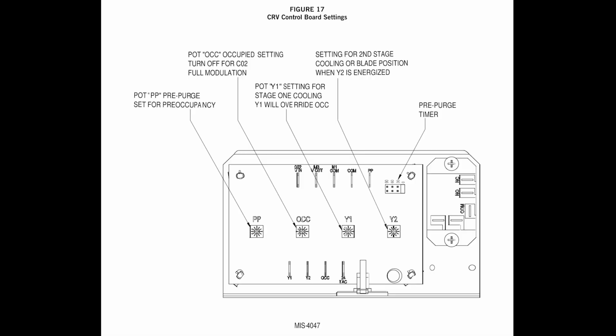The potentiometer marked PP is for pre-purge or pre-occupancy required by Title 24. Pot OCC is the occupied setting and must be turned off if a CO2 sensor is used. Pot Y1 or Y2 setting is for single-stage compressor units with a brass jumper. Pot Y1 and Y2 setting is for two-stage compressor units without a brass jumper. Blower CFM is different between stages and affects ventilation CFM.